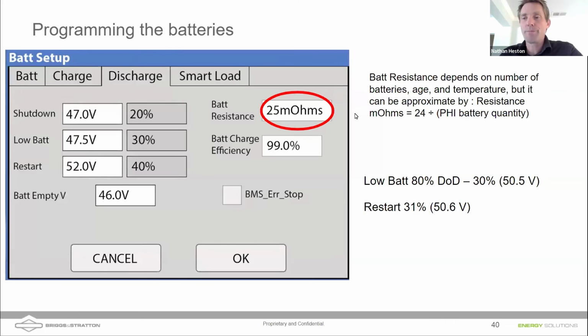Is there a minimum size of SimpliPhi battery or batteries to be compatible with a Sol-Ark 15K? As long as you're using communicating batteries, Ben, you could use just a single or a couple of the communicating batteries. But if that battery bank is too small, you're going to limit the power capabilities of the Sol-Ark 15K. So if you're using an AmpliPhi battery, for instance, you would need a minimum of 7 to take advantage of the full 12 kilowatts of power you can get from the 15K. Or if you're using the 6.6 batteries, you would need 3 of them. There's a lot more power output capabilities for them. So thank you for the question. And I do have that in the slides. We'll get those slides sent out to you after the talk.